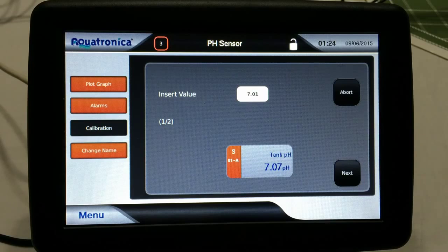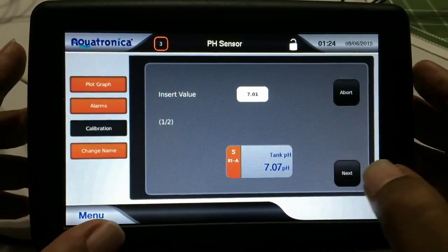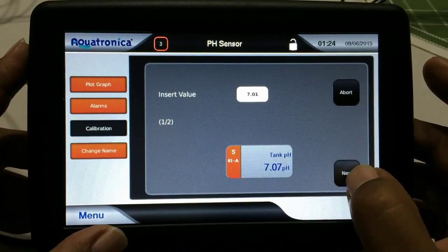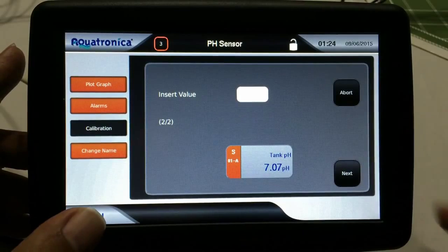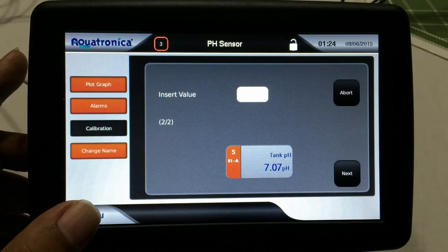I won't have that luxury with the upper value because I'm going to have to rinse off the probe after I take it out of that pouch with some RO water, dry it off again, and put it into the second pouch. And you do that because you don't want to contaminate the pH 10 fluid. So right now this seems pretty good to go. It's pretty settled. So I'm going to press next, and now it's waiting for me to insert the next value.